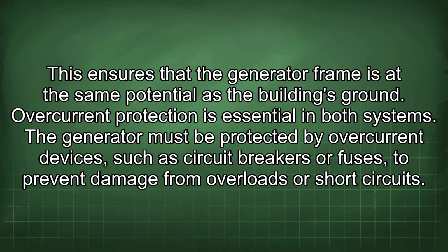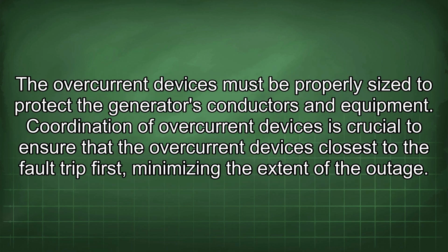Overcurrent protection is essential in both systems. The generator must be protected by overcurrent devices, such as circuit breakers or fuses, to prevent damage from overloads or short circuits. The overcurrent devices must be properly sized to protect the generator's conductors and equipment. Coordination of overcurrent devices is crucial to ensure that the overcurrent device closest to the fault trips first, minimizing the extent of the outage.